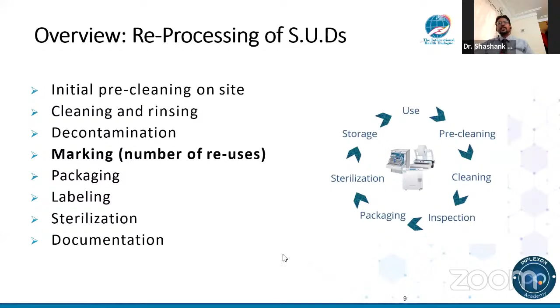Yeah. So this is a very important thing that needs to be checked at the user department. If you're looking at the cath lab, after the cath lab uses the device and does the basic pre-cleaning, it is important that at that stage they check the functionality. For example, we have seen a number of cases where a guide wire has been reused while the tip has gone into the patient and come back out the second time. Then they do a pre-cleaning and try to see if it can be reused again.